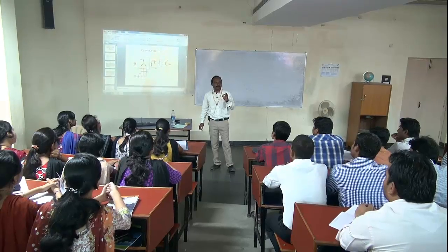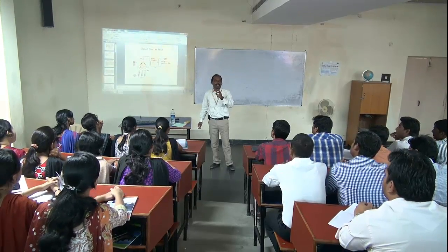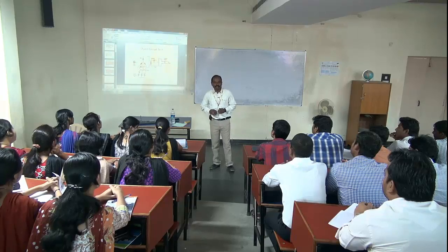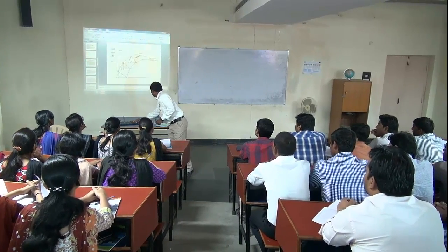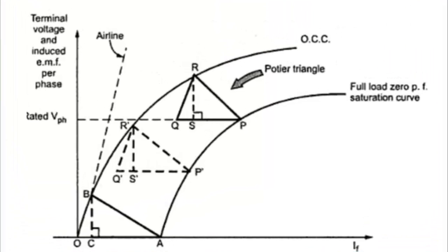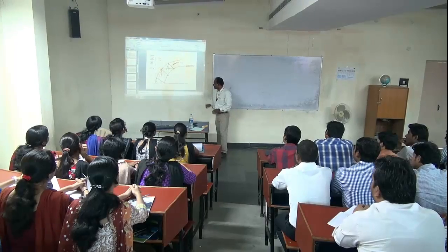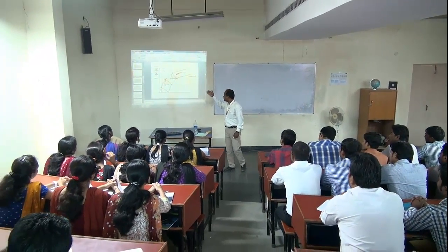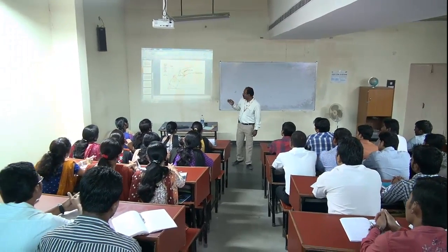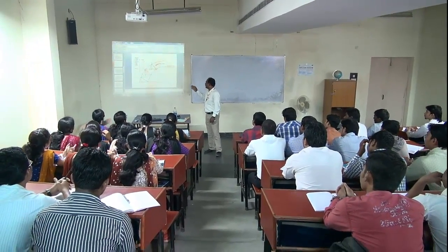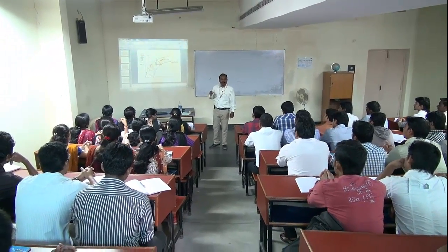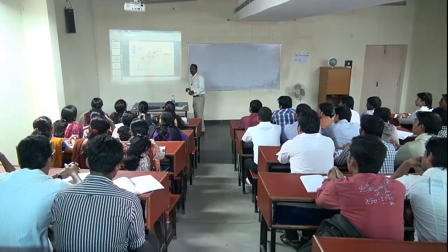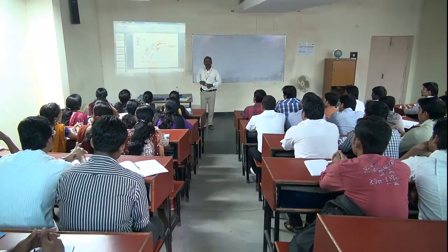By varying the field current using the potential divider, different open circuit voltages are obtained. A graph is drawn between field current on the x-axis and open circuit voltage on the y-axis. This graph is called the OCC — the Open Circuit Characteristic. This completes the open circuit test.